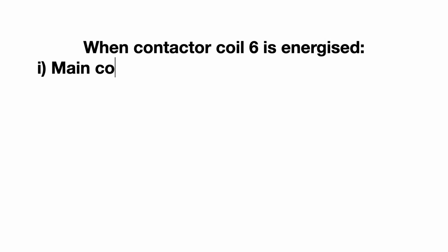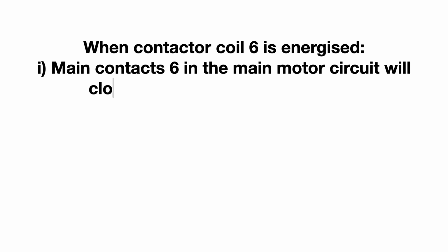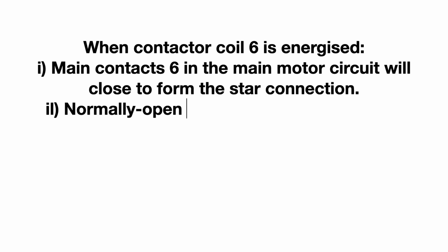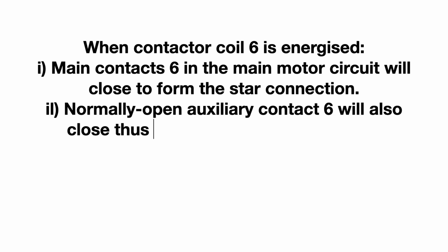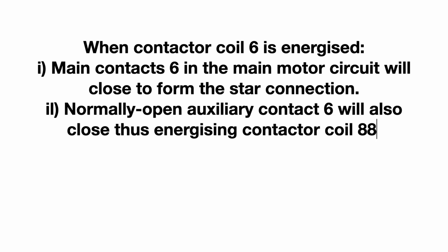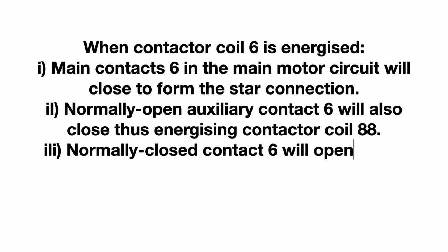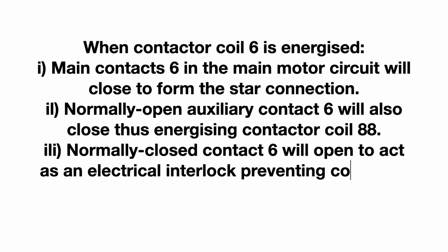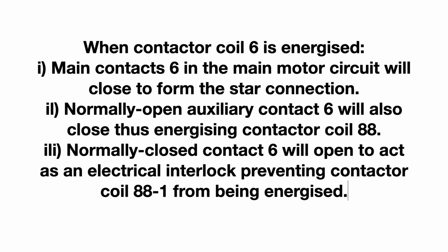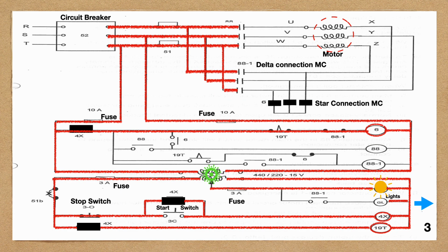When contactor coil 6 is energized, main contacts 6 in the main motor circuit will close to form the star connection. Normally open auxiliary contact 6 will also close, thus energizing contactor coil 88. Normally closed contact 6 will open to act as an electrical interlock, preventing contactor coil 88-1 from being energized.